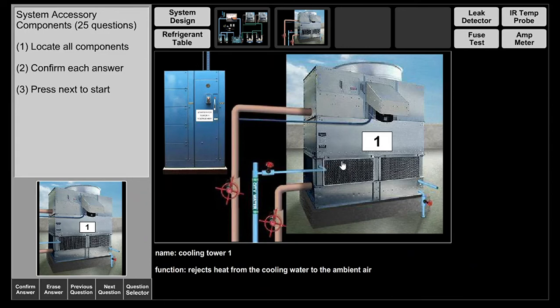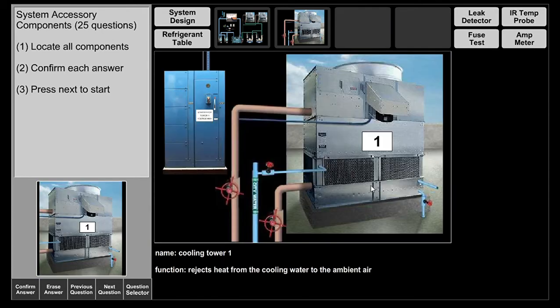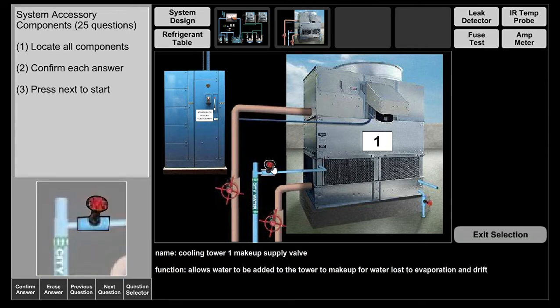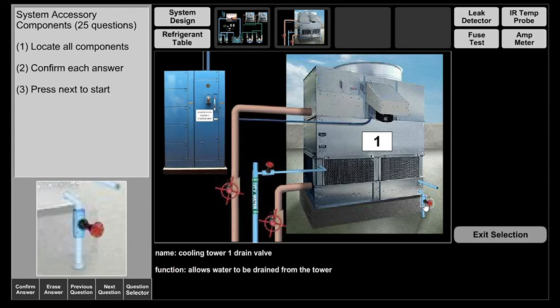As the water comes down through the fill it falls in droplets, collects at the bottom, and by the time it reaches the bottom it's at 75 degrees — or whatever setpoint is set. The setpoint is controlled by the fan cycling on/off or a VFD ramping to a certain speed. There is also a makeup water line to compensate for evaporation losses, an overfill line that drains excess water to prevent overflow, and a drain line used during seasonal shutdown to drain the cooling tower completely for winter.